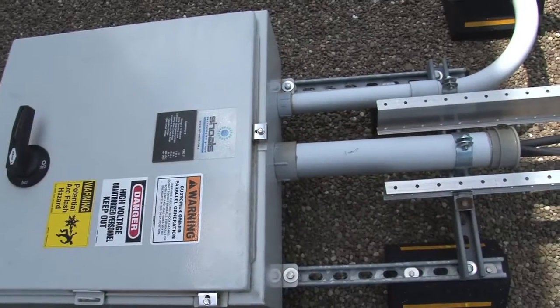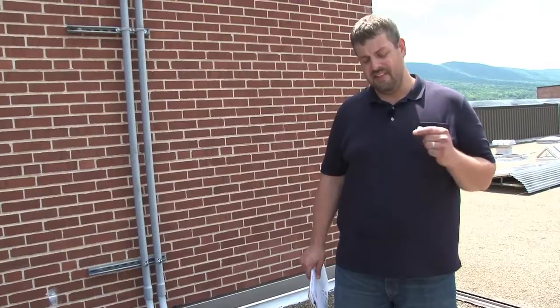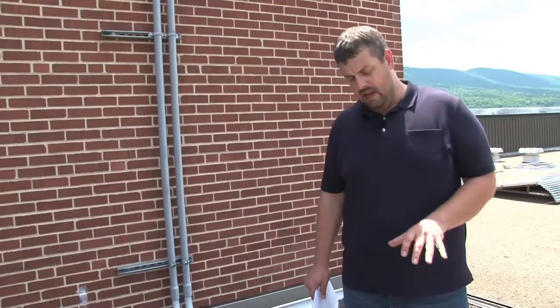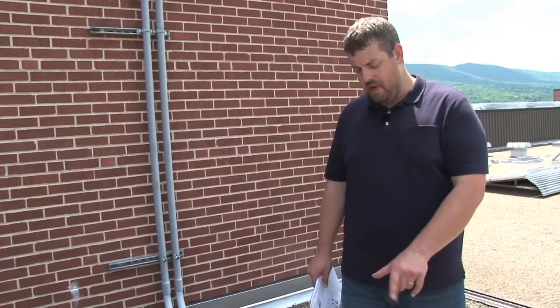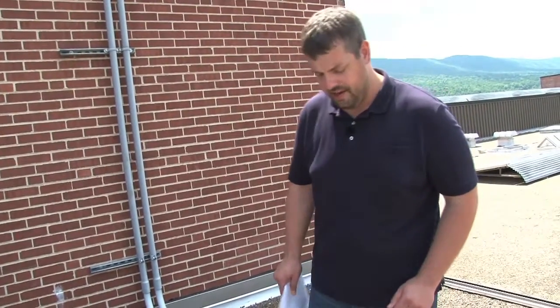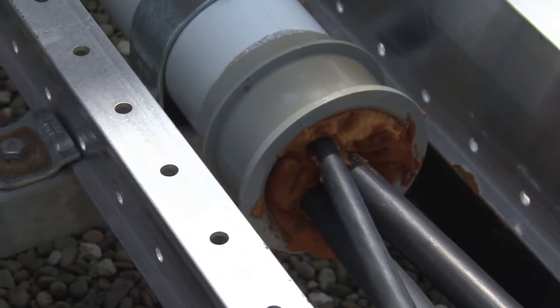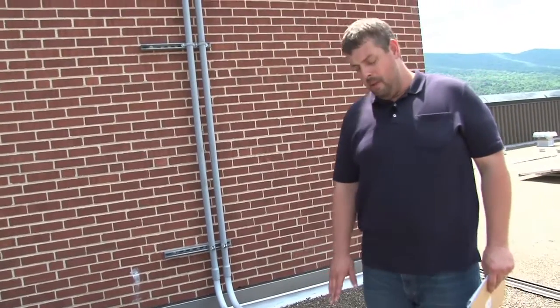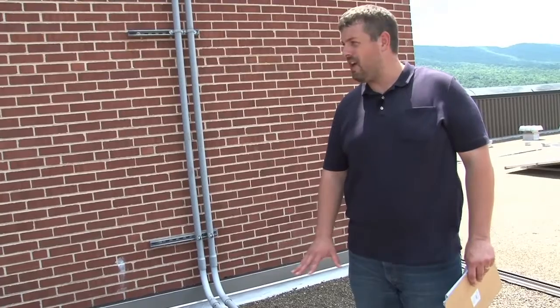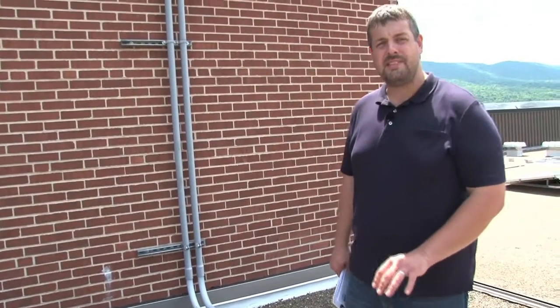This is a short pipe stub that exits the combiner box. What we care about here is that the pipe stub is less than two feet and that the fill of that pipe is less than 43%. As long as we can achieve those two things, we don't have to worry about any conductor derating, and that's going to be really important when we further explore this cable tray system. We need to verify we've got something less than two feet — the fill is definitely less than 43%, although we can calculate it. We also want to make sure the end of this raceway is sealed. That's really important on PV systems: you don't want moisture or water getting into the enclosure, and insects, bees, and bugs will crawl in and make a house out of this box. We can see that on this project, this pipe is sealed properly.